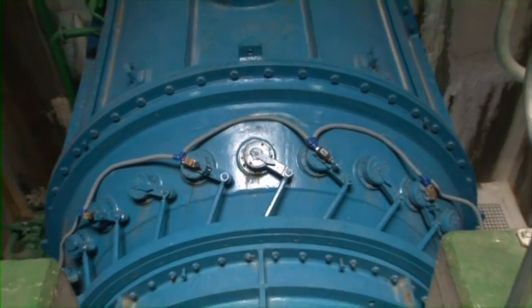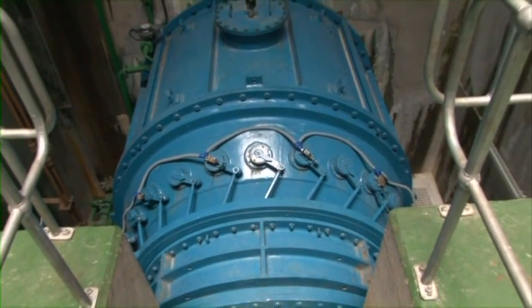The turbine itself is rated to last for about 50 years. They're very robust, they're big pieces of metal. It's not very smart or complex equipment, but the control equipment, being telecommunications equipment, they don't last for too long. They have a lifetime of 5 years and some even less than that, so we replace components in there quite often. The bulk of the rest, like the transformers, they also last for maybe 30 years or 40 years, whereafter refurbishment is required on these equipment.